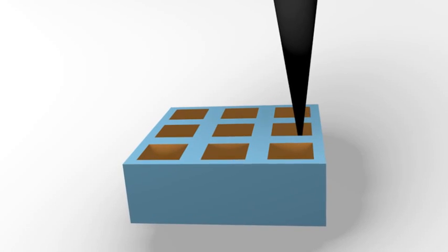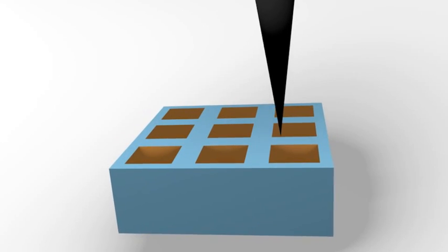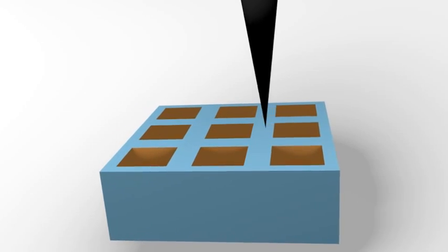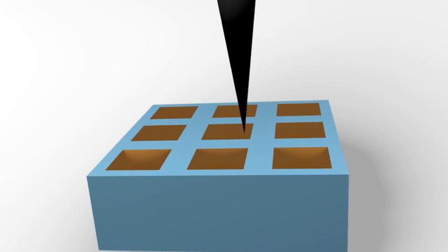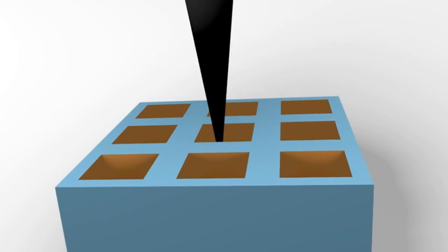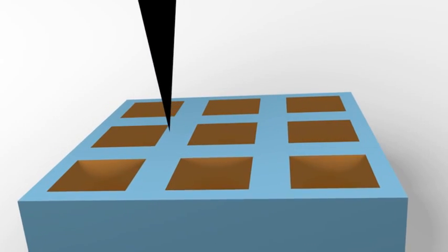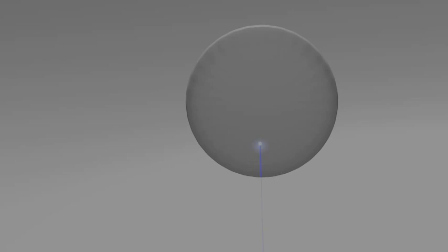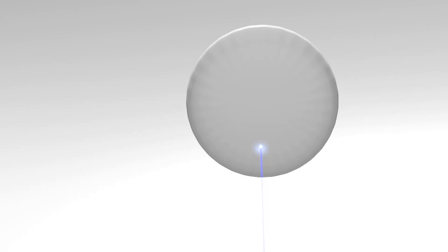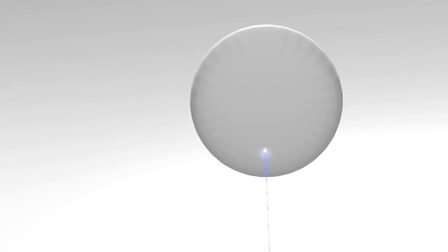The cantilever then moves over the surface following a line by line strategy. As the animation illustrates, when the tip of the cantilever goes down into one of the features on the surface, the angle of the laser beam's reflection changes. This is detected by the photodiode, which gives readings for the scanning of a surface topography.